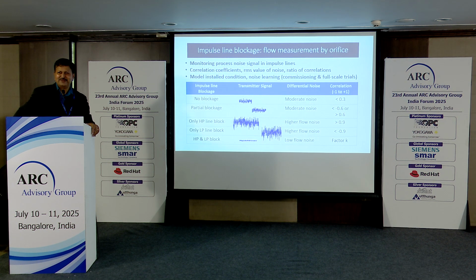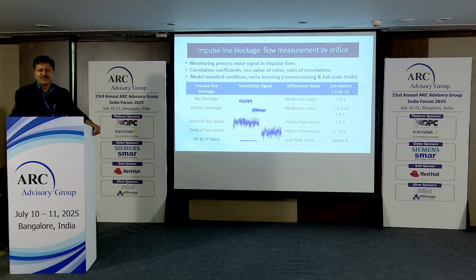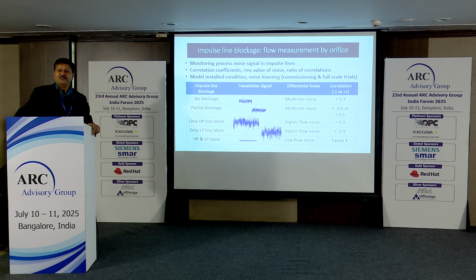Hope in this 20 minutes we can touch upon this, so that we know that this is not a new topic, that is impulse line blockage. When we have flow measurement conventionally by differential pressure devices like orifice, venturi, nozzle, fundamentally this blockage is something we come to see, depending on the fluid that is being processed.